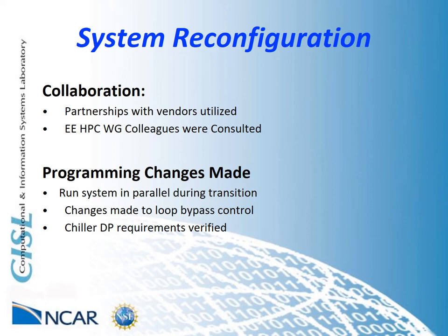The working group suggested that the NWC may want to look at running their cooling system in parallel while the chiller is starting up, explaining they had seen success with this approach at their and/or other sites. After reviewing the possibility of these changes with the NWC partner control vendor, it was determined that the condensing and chilled water system pumps could support the flow of running the systems in parallel. All free and mechanical cooling equipment would run in parallel during the first 5 minutes while the chiller started up. There were also changes done to bypass valve control associated with the loop and verification of DP requirements for the large 1,000-ton centrifugal chiller.